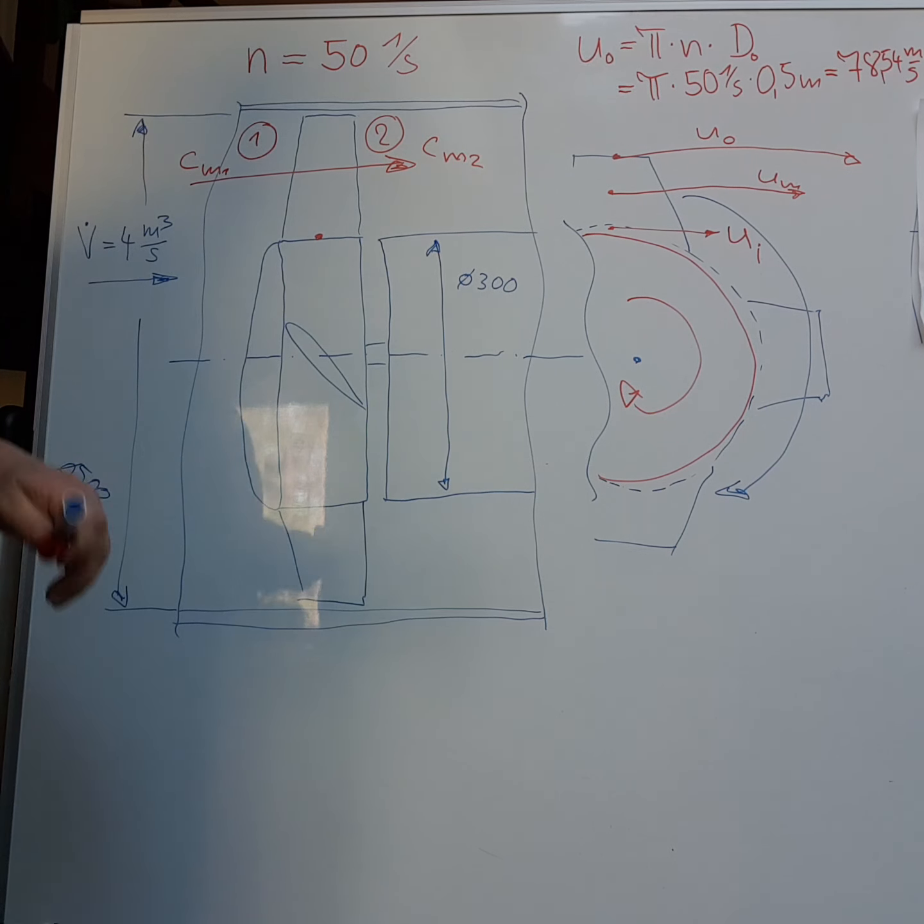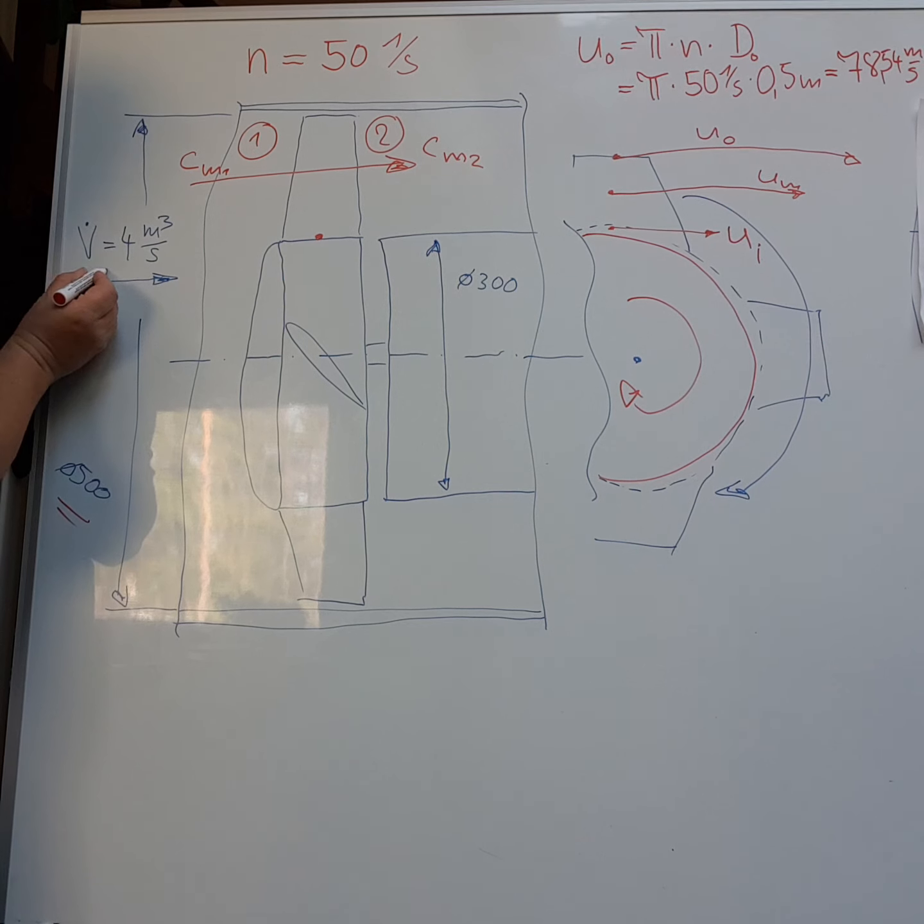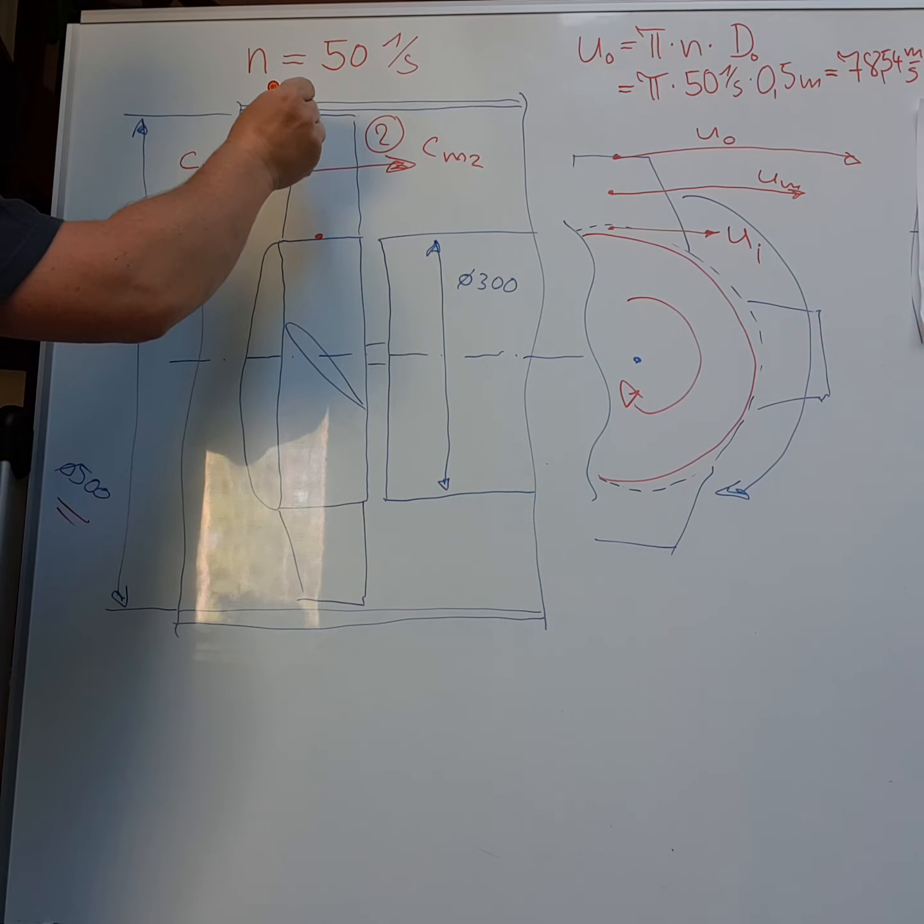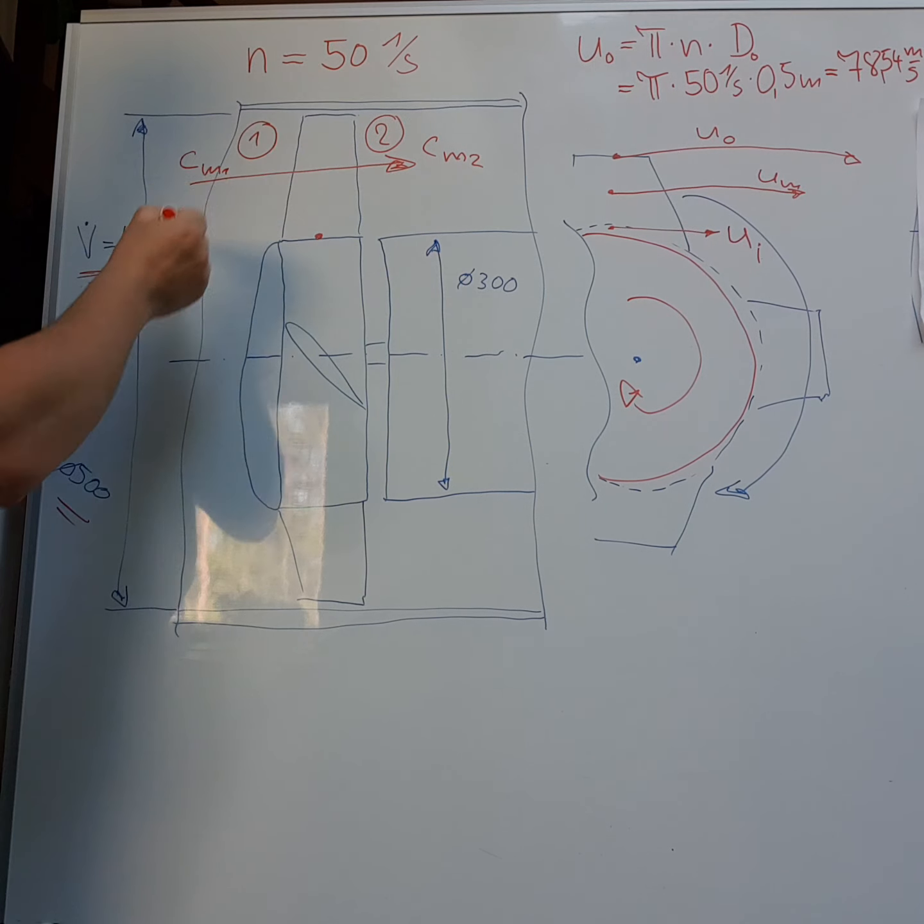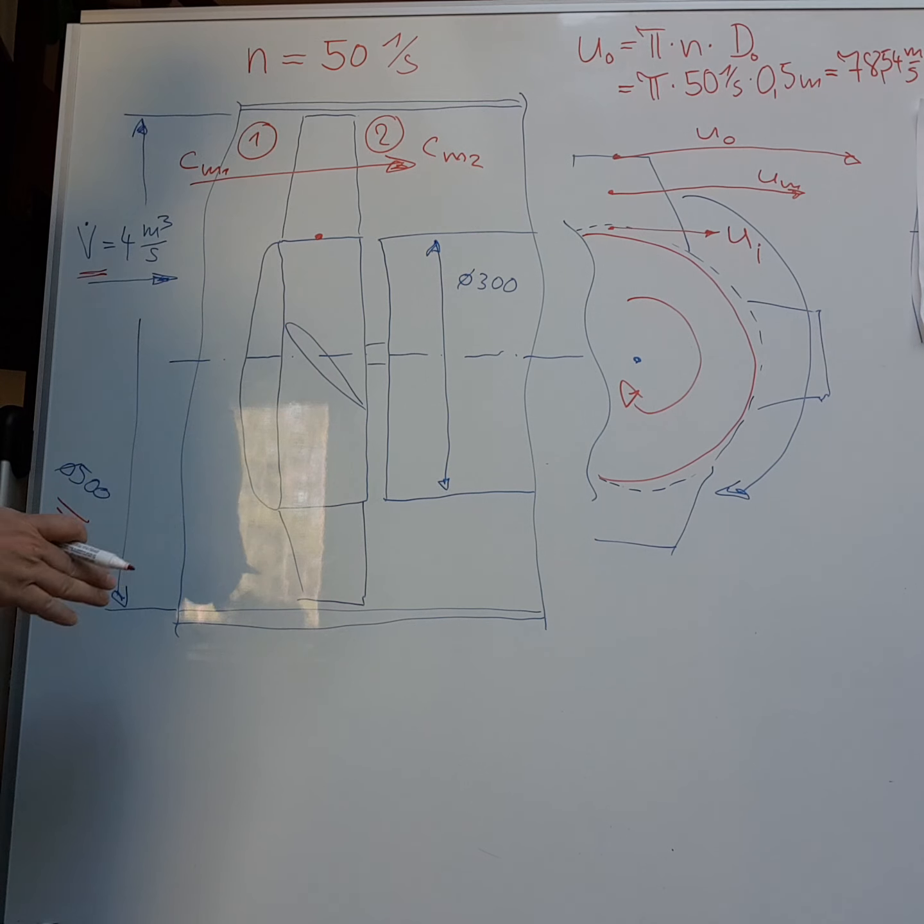So how can we calculate this C value, this velocity value? It is not so difficult because we have the volume flow of the air, 4 cubic meters per second. And if we know the area of this duct, of this pipe, then we can divide the volume flow by the area.